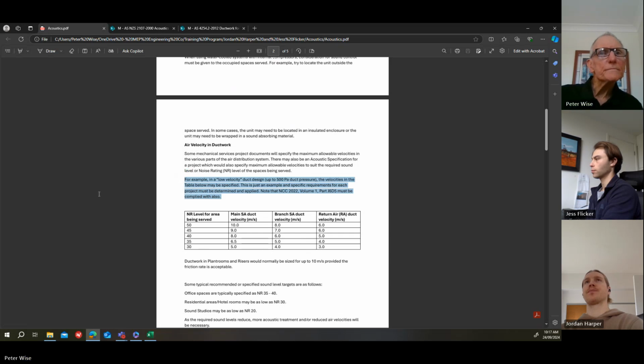I found this somewhere, can't remember where, but this is just an example for low velocity duct design, up to 500 pascals duct pressure. They specified these velocities. Now, don't take this as a guide, well, it's a guide, but don't necessarily use it. This was just what they specified for a particular project. So for NR50, you can run the velocities up to 10 meters a second. For NR30, you have to drop it down to 5 as an example. And return air velocities are reducing as you go down in noise level. Velocities need to reduce as well to keep the noise down.